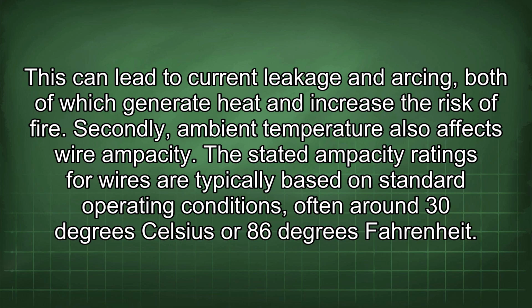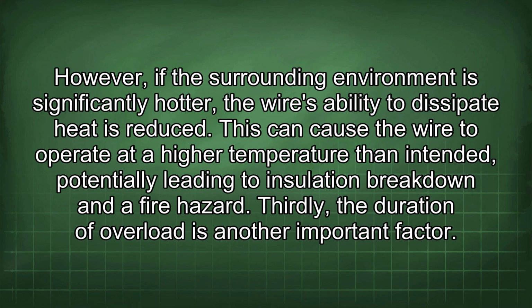Secondly, ambient temperature also affects wire ampacity. The stated ampacity ratings for wires are typically based on standard operating conditions, often around 30 degrees Celsius or 86 degrees Fahrenheit. However, if the surrounding environment is significantly hotter, the wire's ability to dissipate heat is reduced. This can cause the wire to operate at a higher temperature than intended, potentially leading to insulation breakdown and a fire hazard.